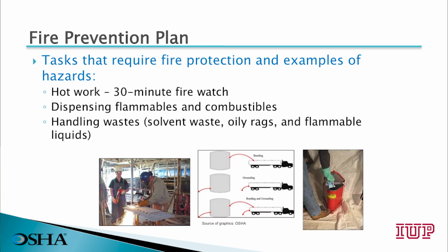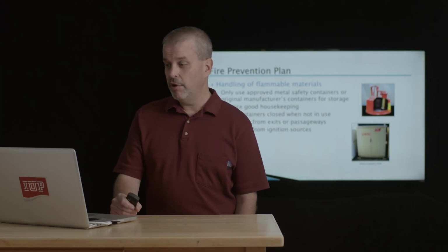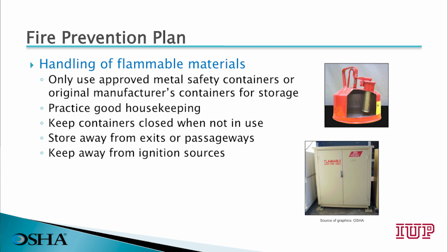Tasks that may require fire protection include hot work. Welding, burning, and cutting outside of any designated area requires a fire watch. Also dispensing any flammable and combustible liquids, and ensuring that we have proper grounding for that equipment, and handling any hazardous waste such as solvents, oily rags, or flammable liquids. If we're handling flammable materials, we need to only use approved safety containers.